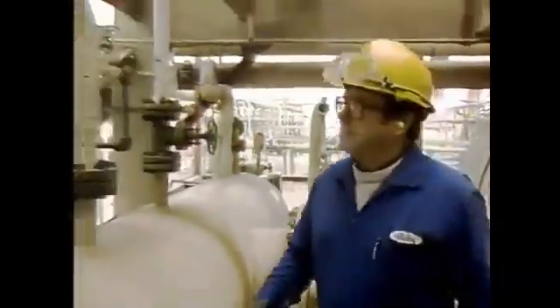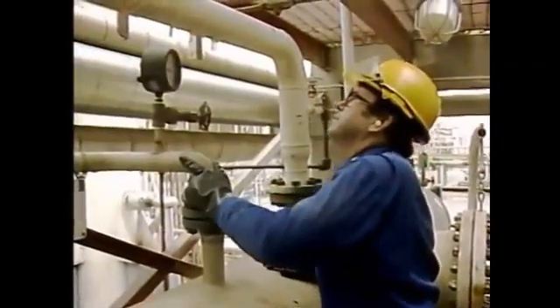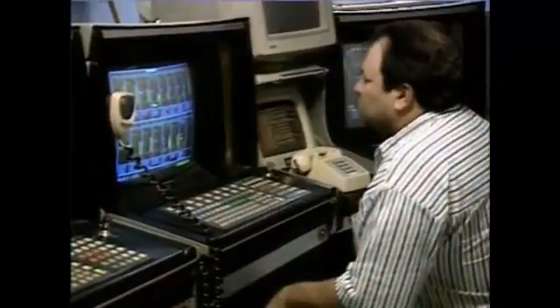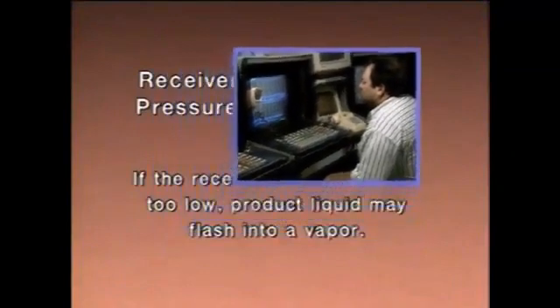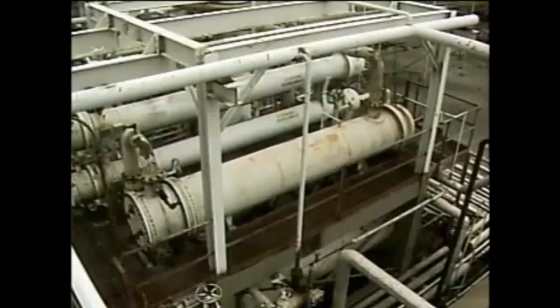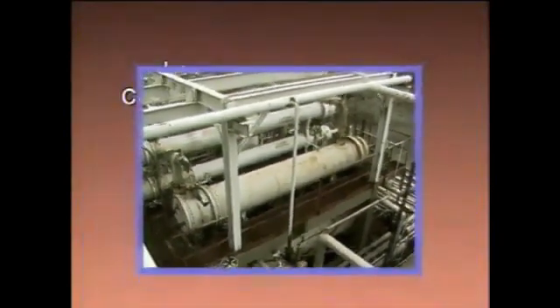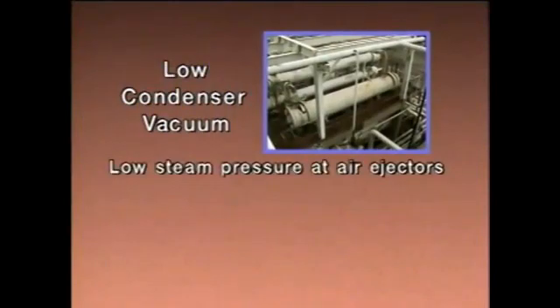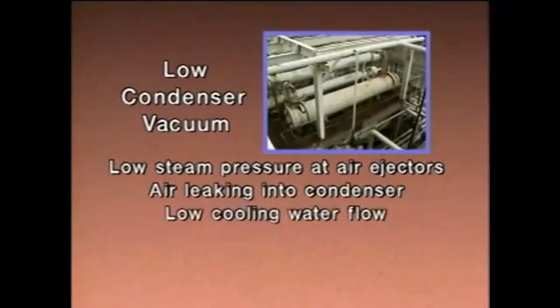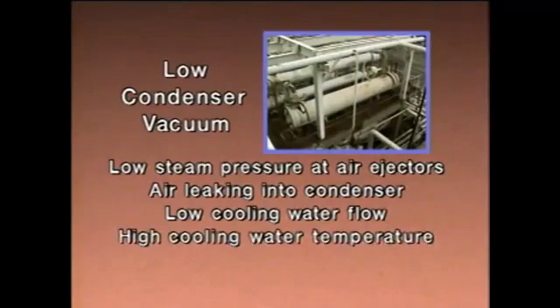Another important operator check is the unit's temperatures and pressure. These indications can be checked on instruments attached to the condenser or on displays in the control room. One pressure reading that is important to check is the receiver's pressure — if the pressure in the receiver drops too low, the product liquid may flash back into a vapor. On condensers that operate under a vacuum, insufficient vacuum may affect efficiency. Too little vacuum can result from steam pressure being too low at the air ejectors, from air leaking into the condenser, from too little cooling water flow, or from the cooling water temperature being too high.